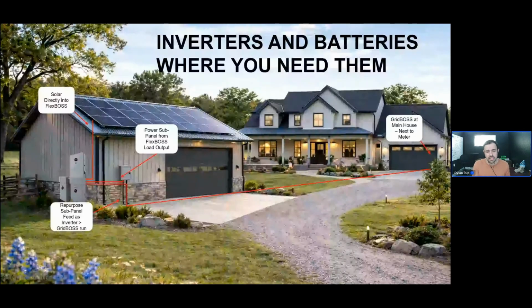And we've done that by placing the energy storage system and the inverter where they need to be, and only had to perform minimal site disruption for a situation that traditionally would require either trenching or multiple significant conductor runs in order to pull off whole home backup on this type of system. And we've seen this in the field multiple times. This is actually a common scenario for especially our customer base in Texas, who might be in a little bit more rural location, might have a building on site that's not necessarily where their main meter is located, and they want an easy means to put solar on that building, but still have that power available at the house or where the main meter for the site is located.